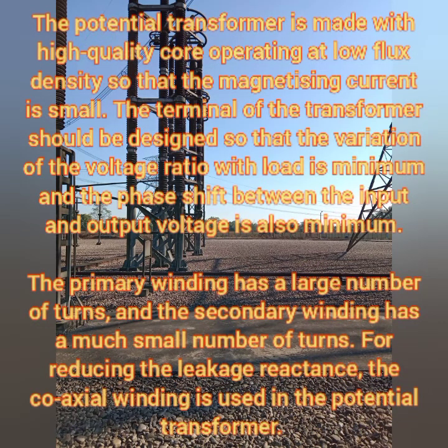Next, a potential transformer is made with a high quality core operating at a low flux density so that the magnetizing current is small. The terminals of the transformer should be designed so that the variation of the voltage ratio with load is minimum and the phase shift between the input and the output voltage is minimum. The primary winding has a large number of turns and the secondary winding has a small number of turns. For reducing the leakage reactance, coaxial winding is used.